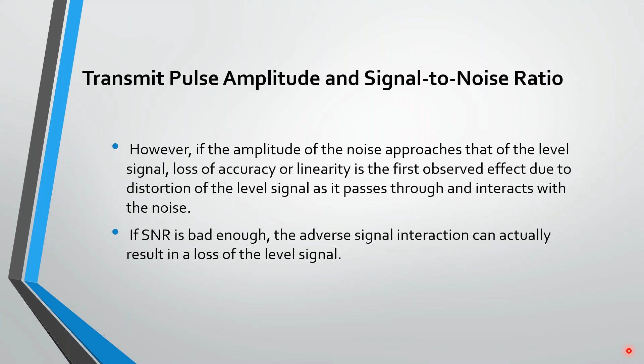We can't just increase the pulse amplitude, the signal strength, and hope that the signal to noise ratio will get better. It won't. There are other things we need to do to make that better. So again, signal to noise ratio tells us the difference between our desired signal and our unwanted noise. Like I said, if the amplitude of the noise approaches the level signal, we're going to lose accuracy. Also, it could result in a loss of signal. With a device, when there's a lot of extraneous noise, that's exactly what will happen. All of a sudden, the device is no longer registering your level. You're not getting a good measurement, and you look at an error code, and the error code will say loss of signal or something to that effect.